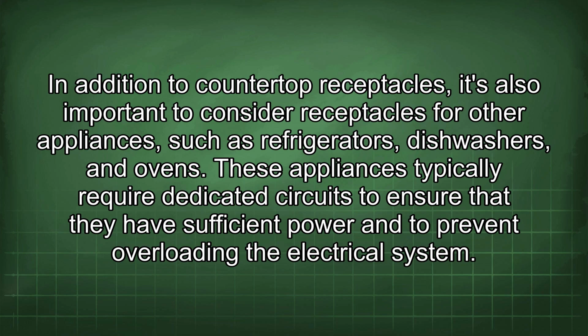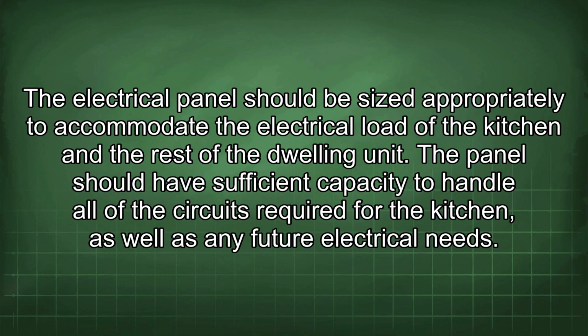and ovens. These appliances typically require dedicated circuits to ensure that they have sufficient power and to prevent overloading the electrical system. The electrical panel should be sized appropriately to accommodate the electrical load of the kitchen and the rest of the dwelling unit. The panel should have sufficient capacity to handle all of the circuits required for the kitchen, as well as any future electrical needs.